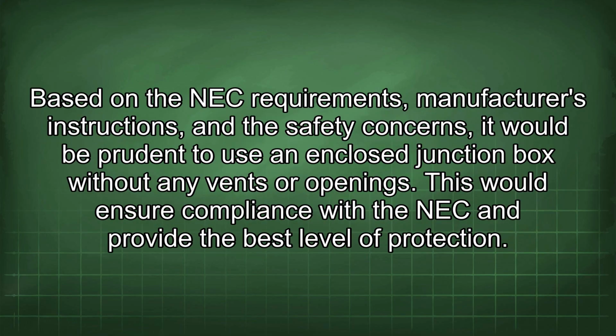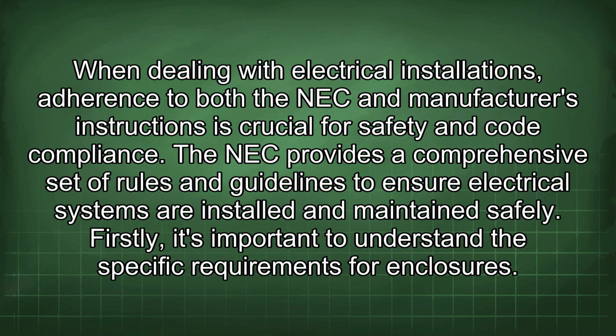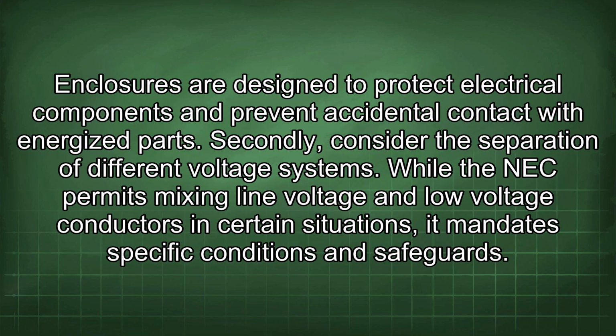Based on the NEC requirements, manufacturer's instructions, and the safety concerns, it would be prudent to use an enclosed junction box without any vents or openings. This would ensure compliance with the NEC and provide the best level of protection. When dealing with electrical installations, adherence to both the NEC and manufacturer's instructions is crucial for safety and code compliance. The NEC provides a comprehensive set of rules and guidelines to ensure electrical systems are installed and maintained safely. Firstly, it's important to understand the specific requirements for enclosures. Enclosures are designed to protect electrical components and prevent accidental contact with energized parts.